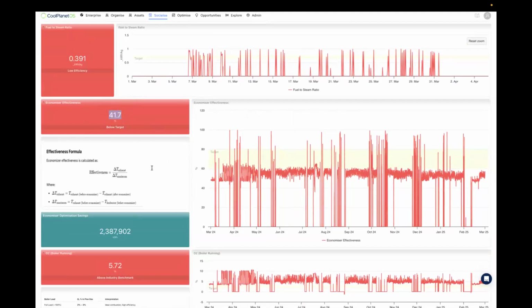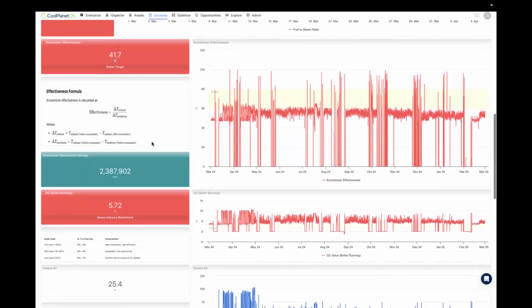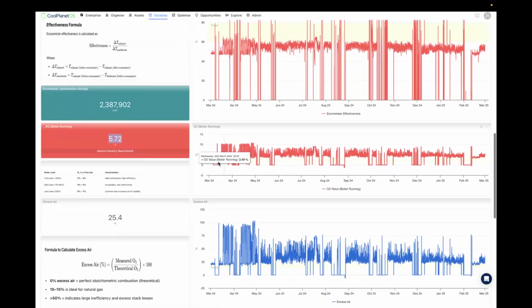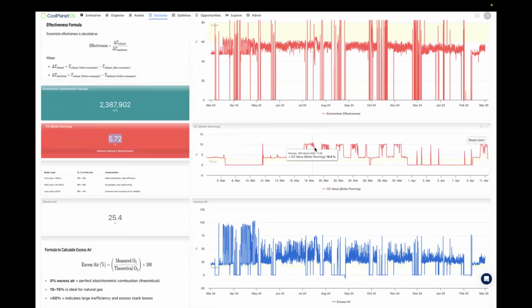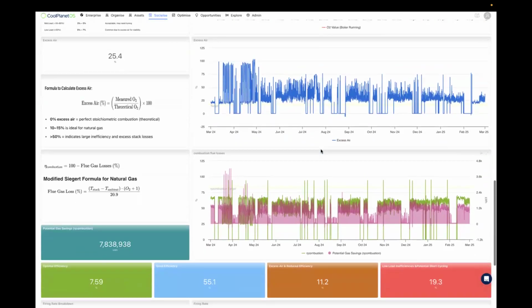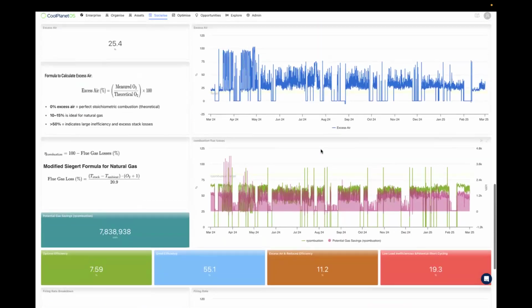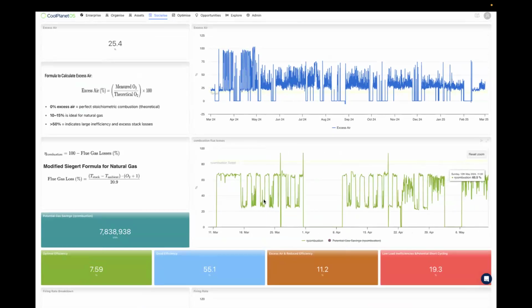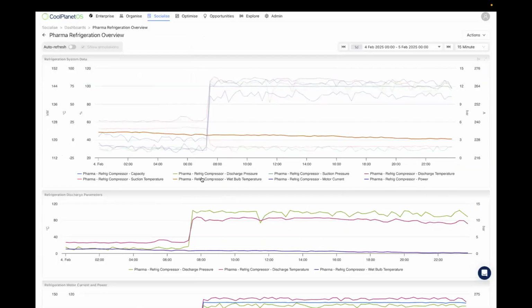And what's also very, very important is to understand where these virtual or soft sensors, these calculated data points, come from. So we always display the calculations, the equations behind each particular output. So you can see very low economizer effectiveness, very high O2 in the combustion cycle versus industry standard, way above where you'd expect. Then we're looking at things like the combustion efficiency of the burner and comparing that versus industry standard. And again, it's well below. So the next step here is to increase all of those KPIs, get the efficiency of all three boilers up to acceptable outputs.